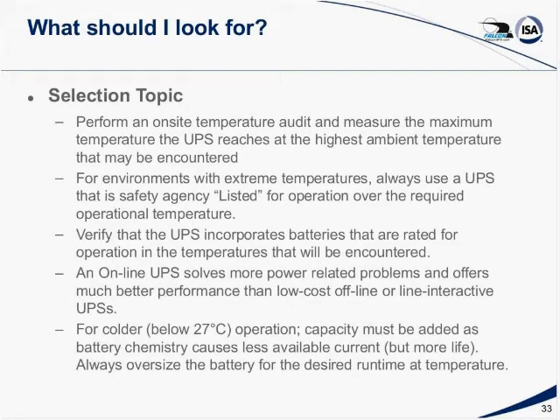The other issue is the battery life. If you use a standard 5-year VRLA battery and try to use it at 65C, the life is going to be a matter of days. The battery will become defective. There's also a safety issue there. Using batteries outside the temperature range can bring up a whole myriad of safety issues.